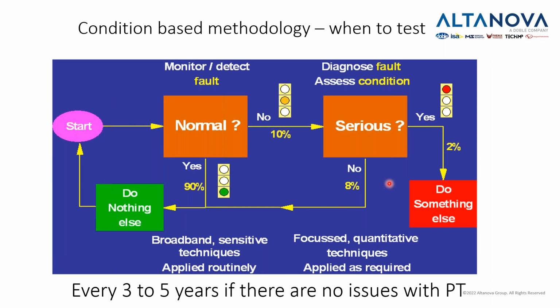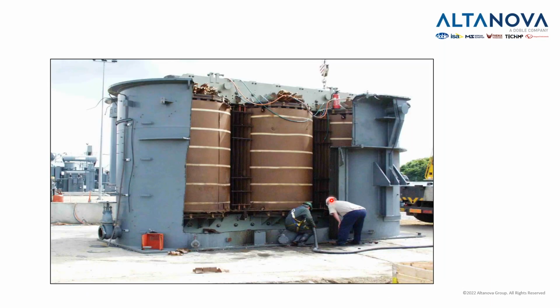This is an interesting chart which will tell you how to decide when or what to do with the transformer. If everything is okay with the transformer, which in 90% of the cases is, then we don't have to do anything else. But if it's not okay, which is in only 10% of the cases, we have to check whether this is serious or not. If it's not, we don't have to do anything else. But if it is, then we have to do something. So this is the most basic algorithm to help you understand what and when you should do it. In general, let's say one rule which we saw accepted throughout the world is that a transformer, if everything is okay with it, needs to be tested every 3 to 5 years.